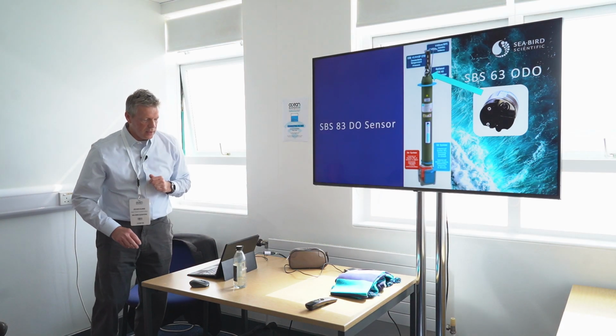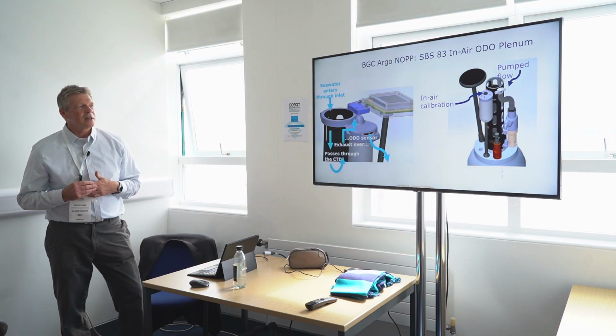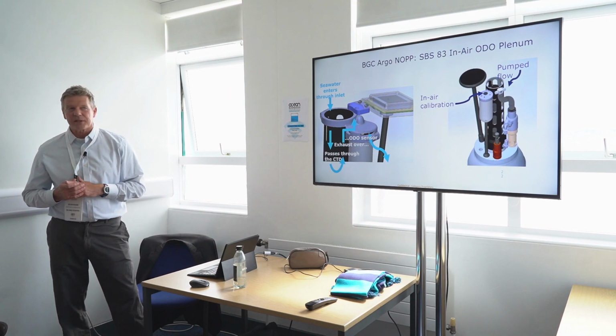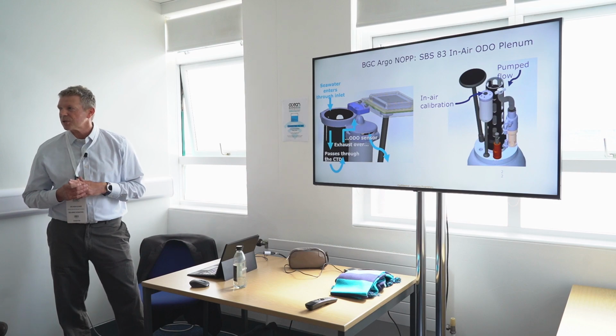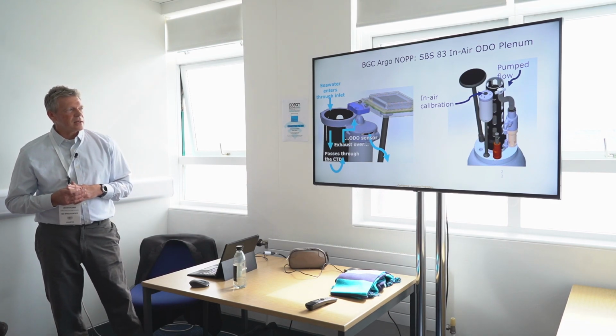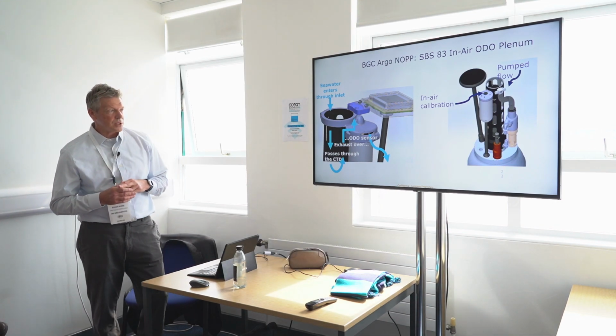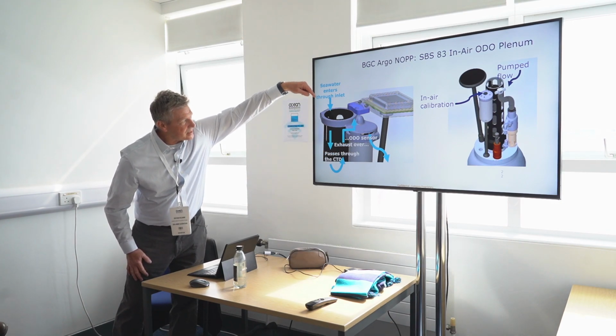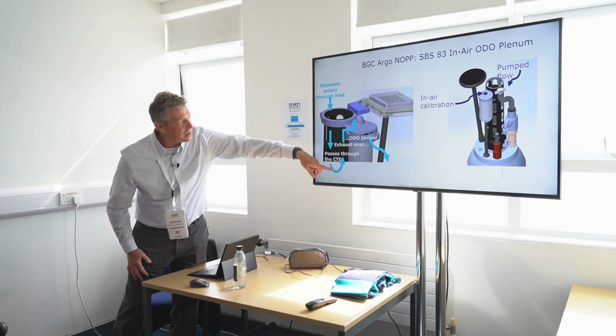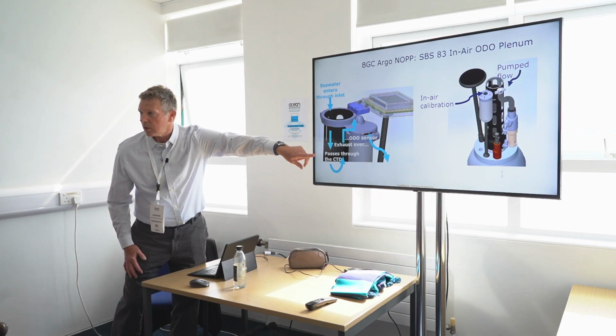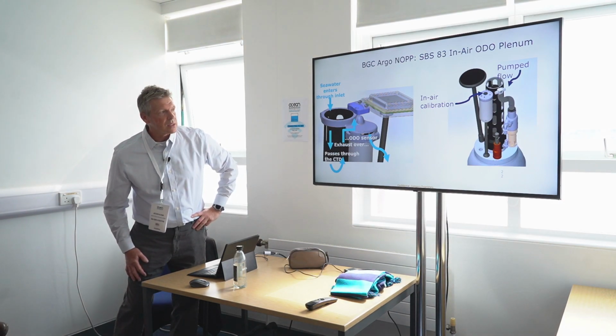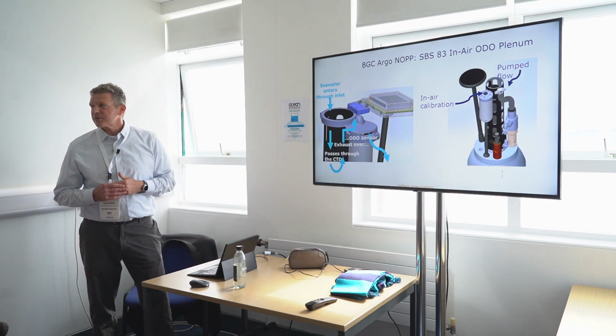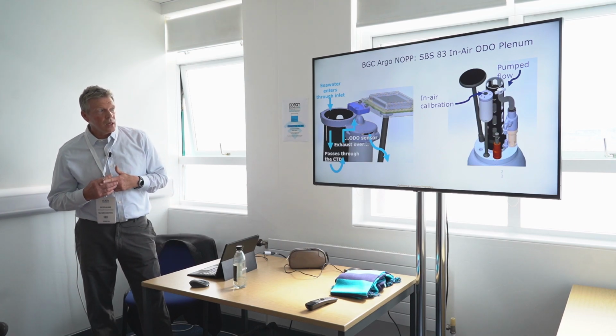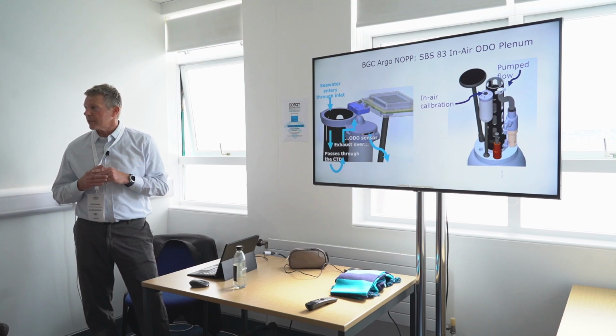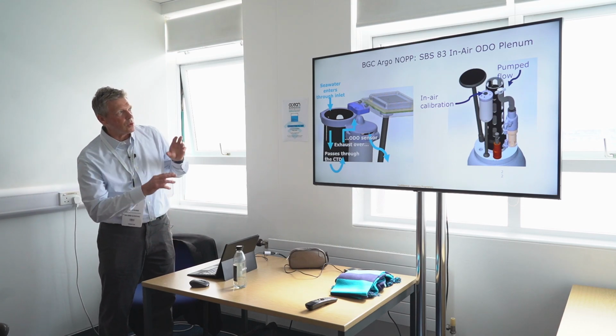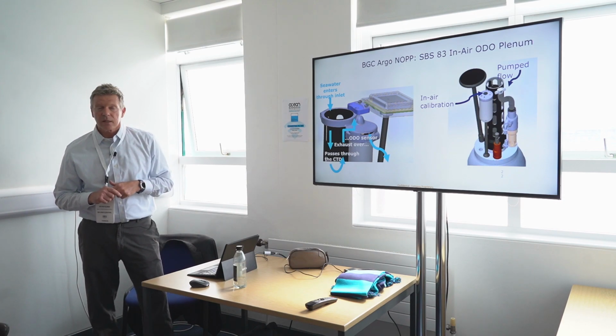So we were approached to see if we can take advantage of the better time response of the 63 sensor and turn that into a sensor that's also calibratable in air. And the way we achieve that is we're repositioning the sensor at the end of the flow path. So you basically think of the water as coming in here, going through the CTD, and then coming back out, and it's exhausted over the optical oxygen sensor in the new design. So that gives you the best of both worlds, where you still have the advantage of the pump flow, so the faster time response of the sensor, but also the ability to do an in-air calibration. So at least that was the idea. And there was a whole NOPP project around that to really make that technology come to life.